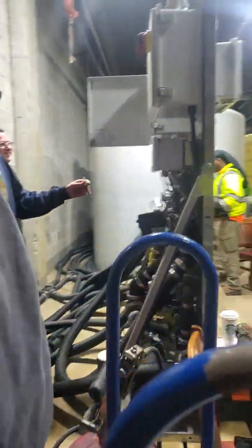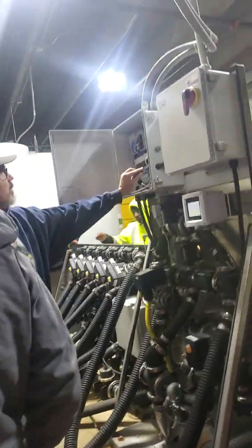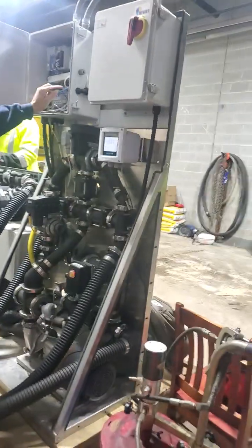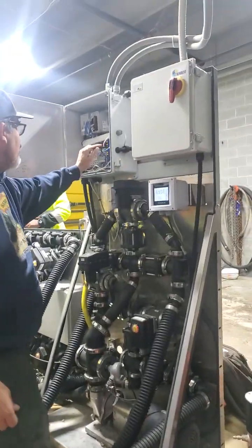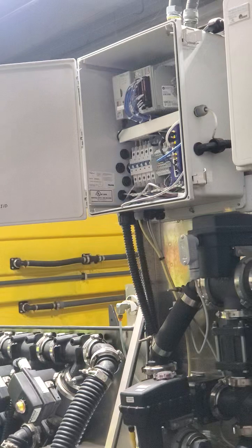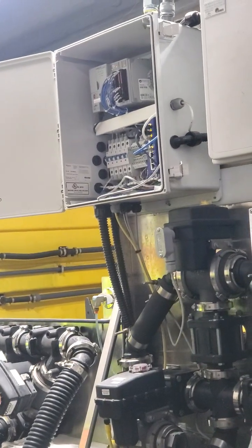A couple at a time. See how this button is out right there? These two, this is your safety relay here. We've got one button on there that says fault. If I clear this and then hit reset, what color is it? Now I've got 3 lights. Okay, only got 1 light, 2 lights are out. It's just a way to check, you know, if the pump doesn't start and you hit reset, come back here and check this.